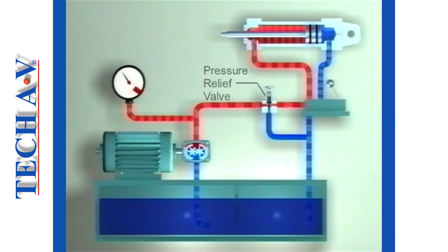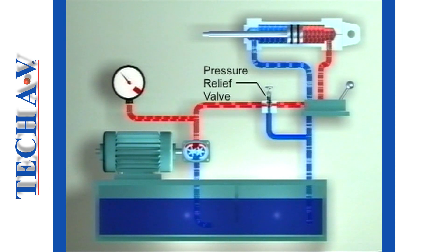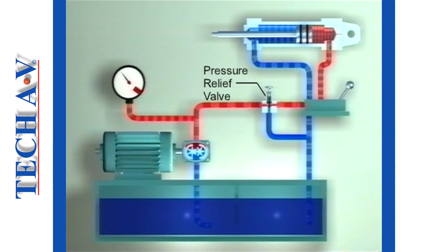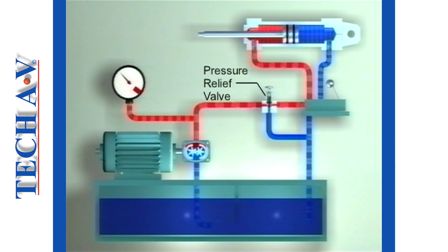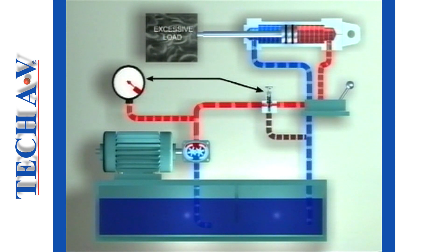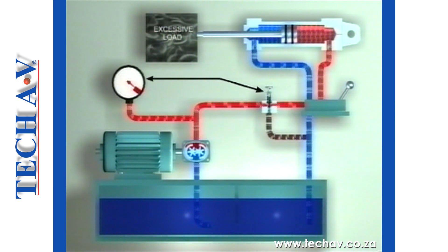Control devices are used primarily for controlling the direction of flow and system pressure. Directional control is necessary to route oil flow to and from the actuators, and directional control valves may be operated manually or automatically. Pressure controls are named according to their main function. In virtually any system there will be a pressure relief valve, whose purpose is to limit pressure buildup to a preset maximum, thus preventing overload. The relief valve, situated in the pump output line, diverts some or all of the pump's output flow into the tank when the set pressure has been reached.